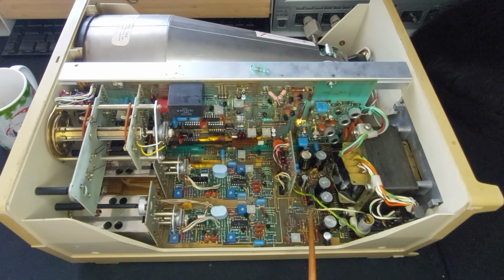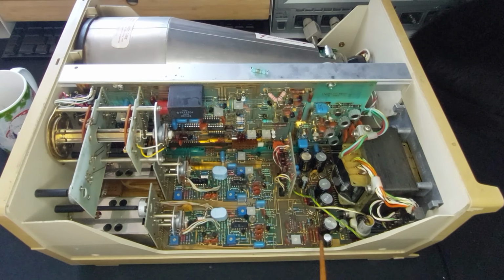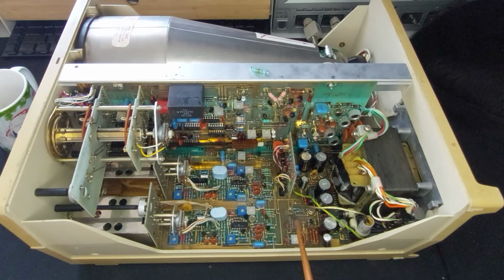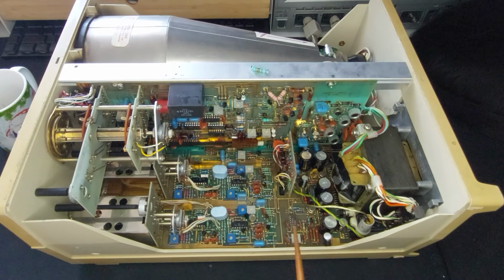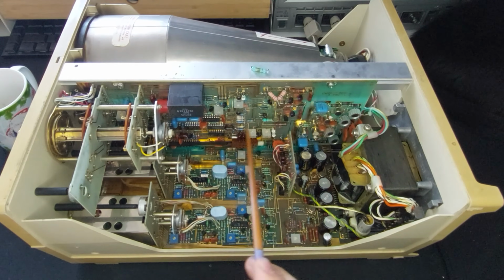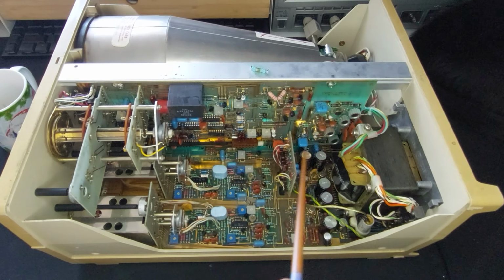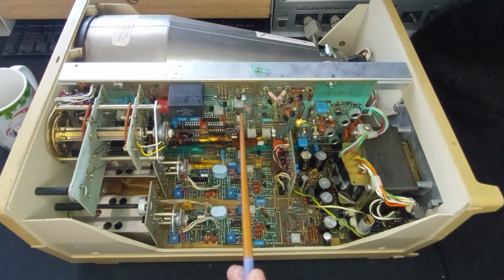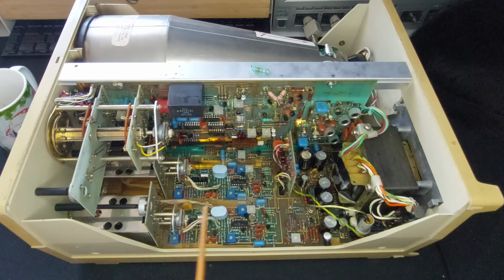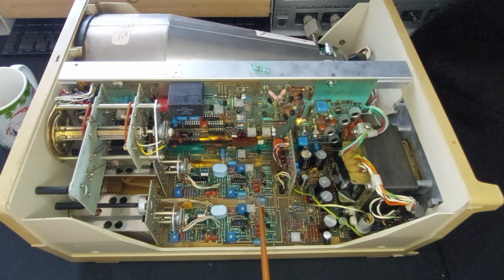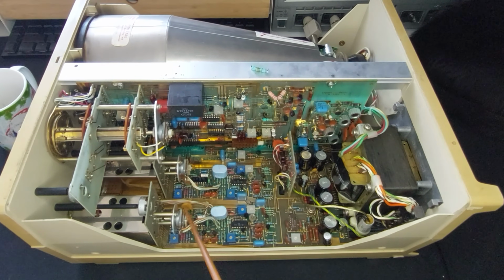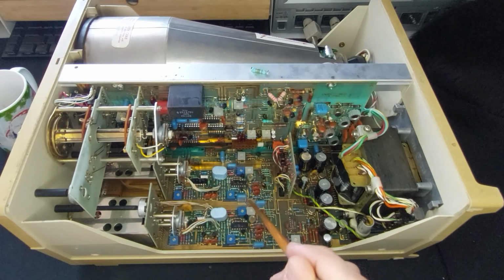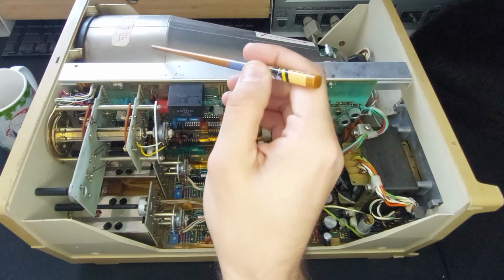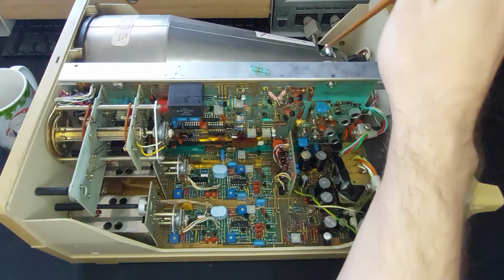This is the power supply section, and we have some capacitors. A couple of them are looking a bit puffy, so that might be the root cause of the second issue. And then we have horizontal amplifier, vertical amplifier for the deflection plates, and there's a sweep generator in this area. I don't know exactly where the delay line for the trigger is. I'm suspecting it's underneath here somewhere, because the other side of the instrument is occupied by the cathode ray tube, and the high voltage generator, the bias supply, is underneath there.